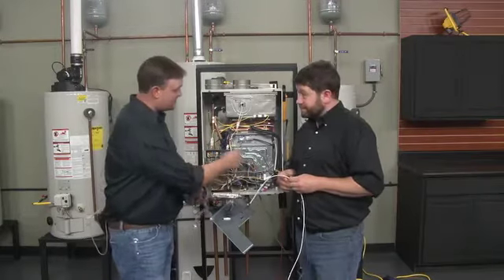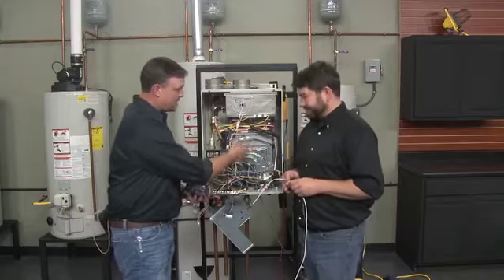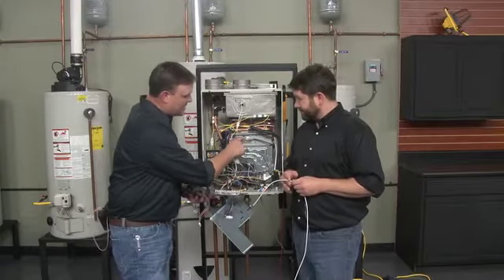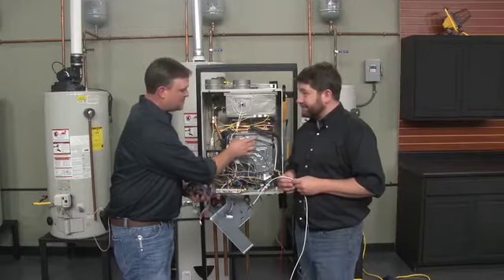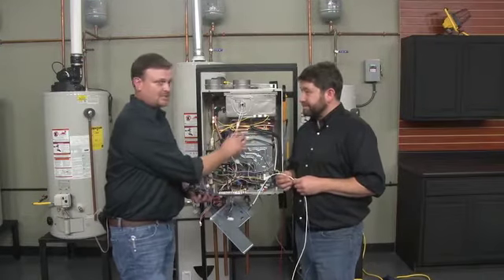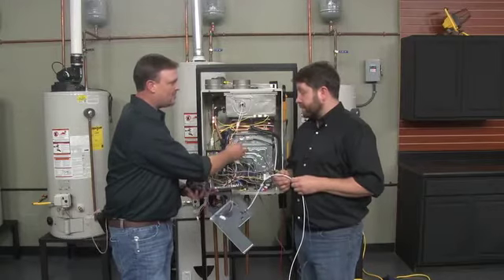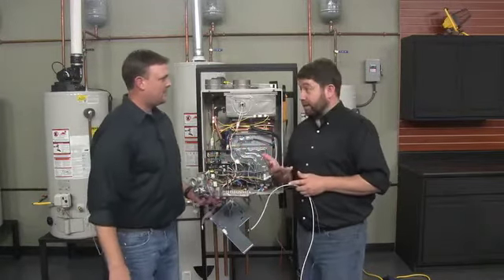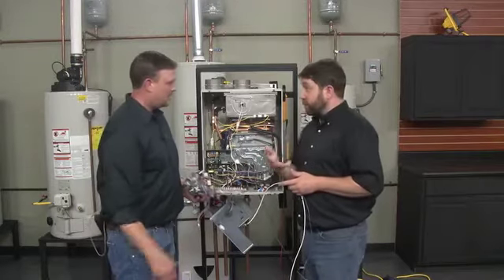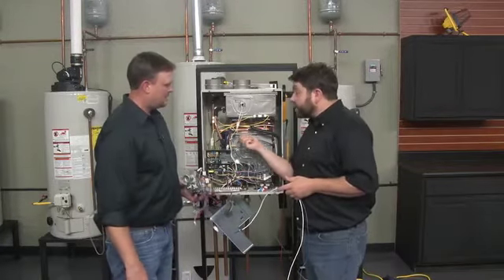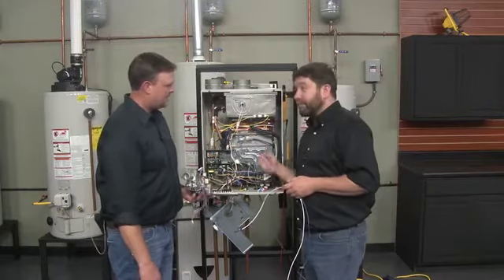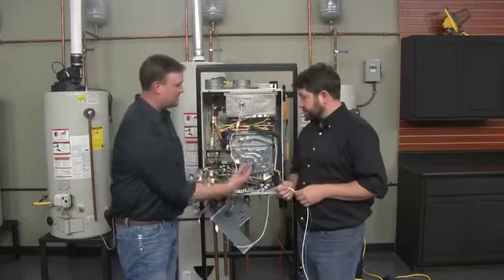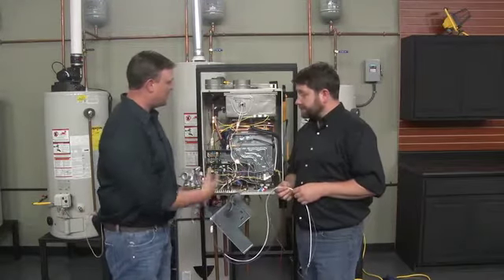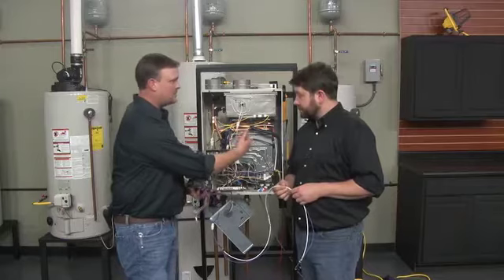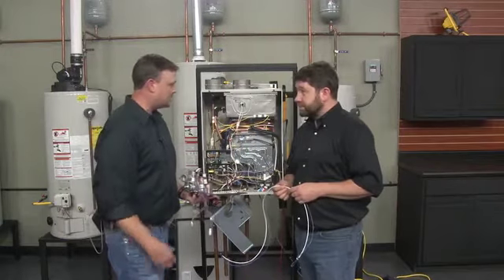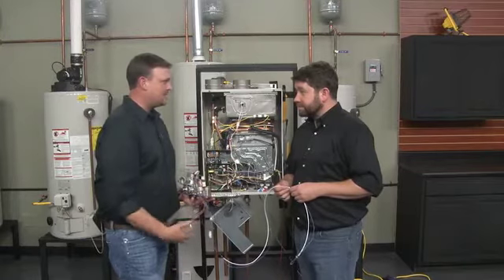Another thing that could trip this is if you do have to take out the flame sensor and igniter, there is a sight glass here, and this bracket actually holds that sight glass in there. That sight glass is not easy to get out, but it can fall out, especially if you pull this out and you're cleaning it. Compressed air will blow it out of there. Or if you're rinsing it with water, you can lose that sight glass, and that definitely will let those hot gases come out, and you can see that it's just right above that. So you don't want to do that, and if that does happen, it's going to open that up. But really, most of the time, you'd be dealing with the buildup on the inside of that water passage, and if you get a breach in the heat exchanger, it'll have to be replaced.